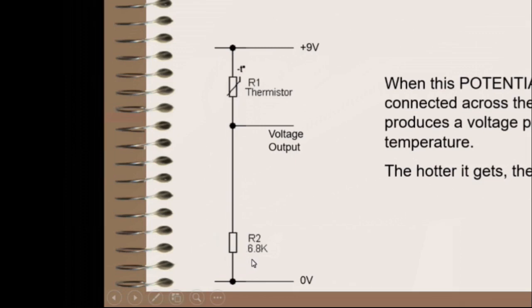R2 is a fixed resistor, 6.8 kiloohms. R1 is your thermistor, and its resistance varies according to temperature. So as temperature goes up, its resistance goes down. This is all where you need to understand voltage drop. If this resistance goes down and this stays the same, then the amount of voltage at this point right here would be higher. If we go the other way, and again, this stays the same, this resistance goes up, then the realized voltage at this point will go down. So once again, the hotter it gets, the higher the voltage.